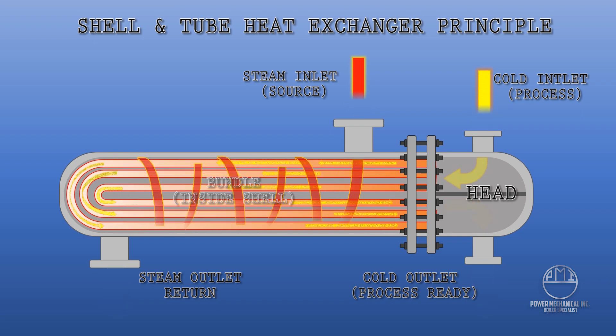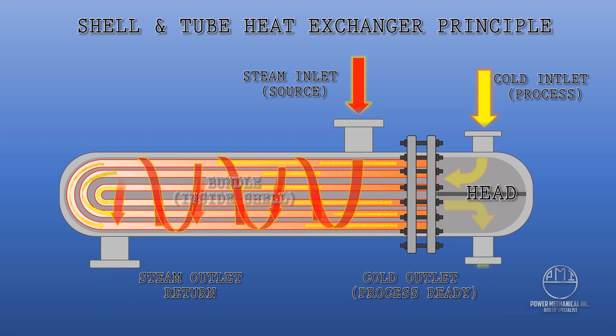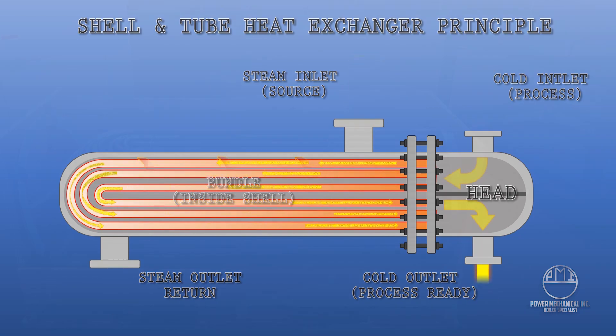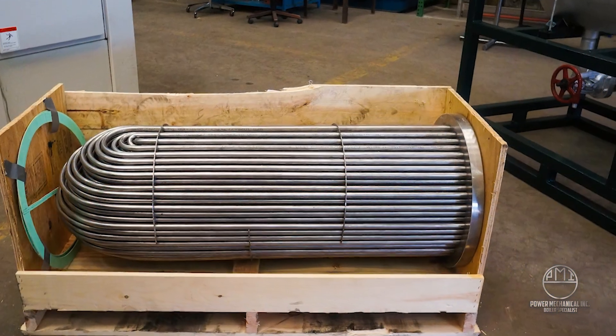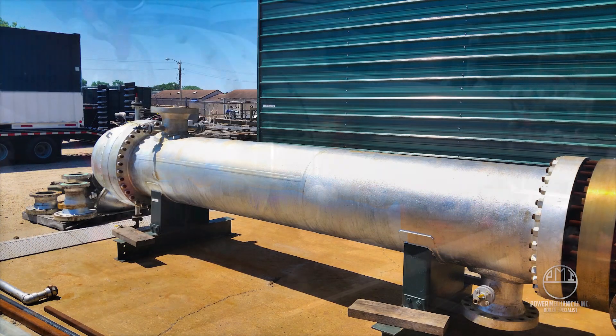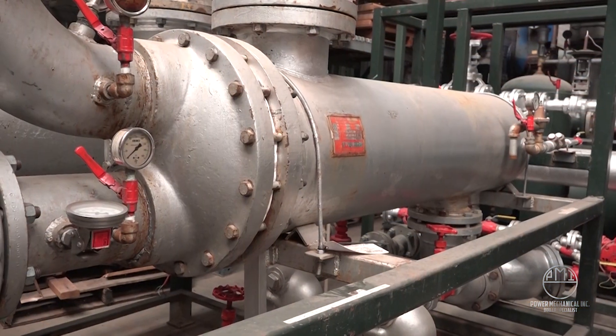The medium circulates through as the heat source steam is circulated around the bundle by way of baffles within the shell. The process medium exits the heat exchanger at the desired temperature for further use. The more tubes within the heat exchanger, the more heat transfer possible.